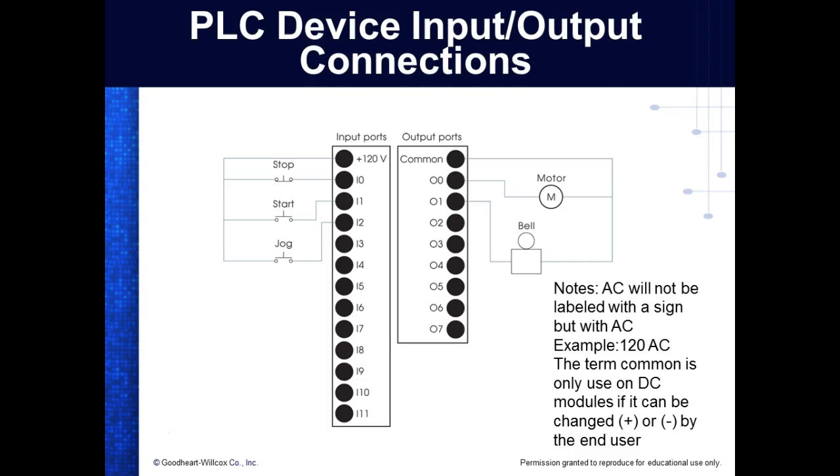Good gracious, these things probably pull 2 milliamps. They're not even loaded. Well, we can run that. Generically, the outputs on most PLCs are rated at around 2 amps. But that's just generically, right? You understand? If you want to find out how much current is available on those outputs, you need to look up the model number and find that online. That makes sense?